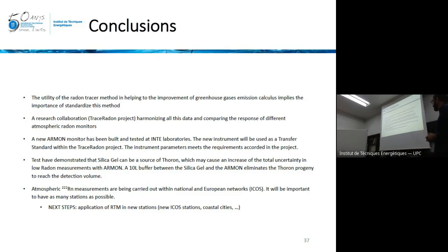Tests have demonstrated that silica gel may cause an increase in the total uncertainty of low radon measurements with ARMON.